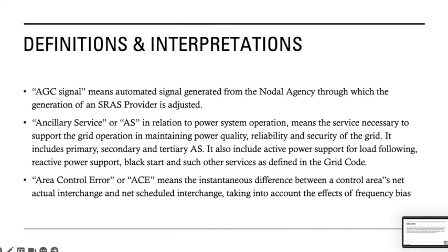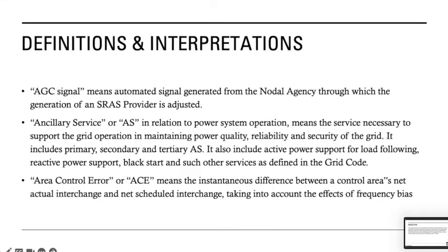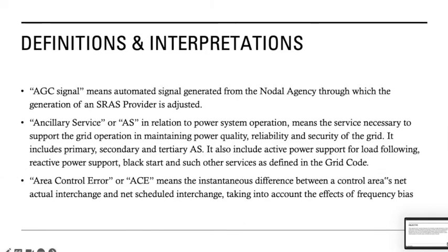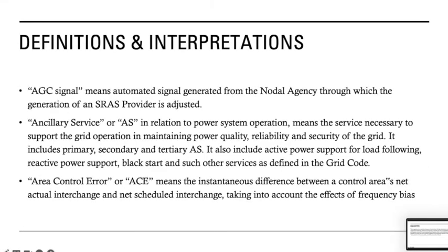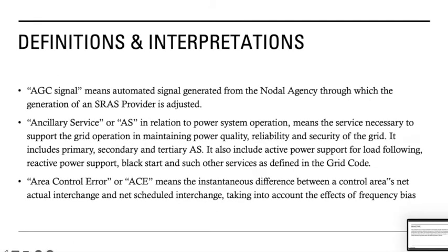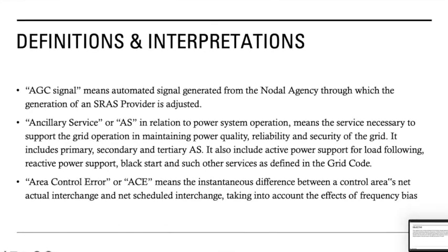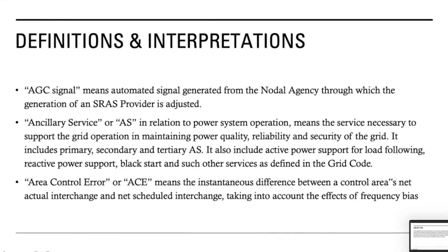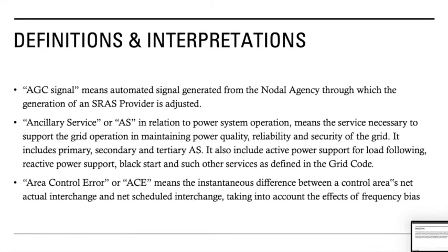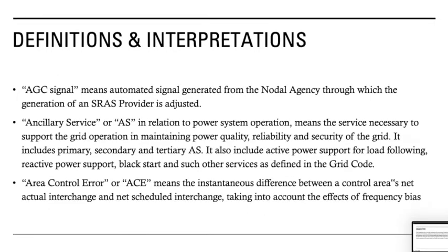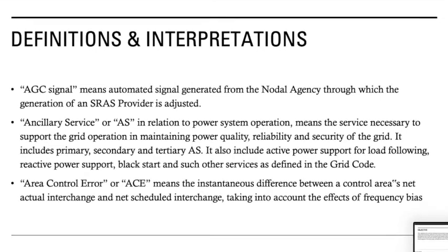Basically, it means that the ancillary service provider would have limited control on its generation. The grid has the option to increase 10 MW, 20 MW, 30 MW or decrease 10 MW, 30 MW or any number, as per the maximum operating capacity of that unit. So the grid can basically ramp that unit up and down in order to maintain the frequency. The signal which is generated would be called the AGC signal.